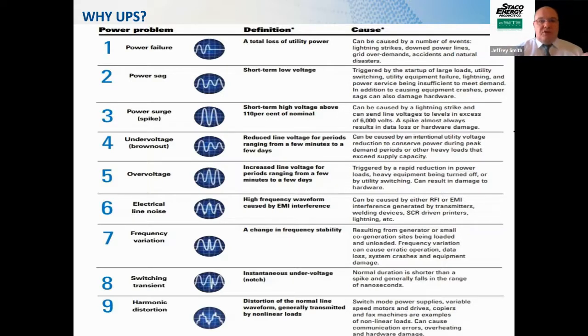The UPS system, we're able to keep the power up, and a lot of times without even going to battery in brownout situations. Over voltage situations, electrical noise getting on the lines, frequency variations. Typically, this is when you have a power outage, and in the United States, I'm talking mainly in power outage, then you go to generators. Sometimes the generators, if they're lightly loaded, they can vary a little bit with the frequency. Outside the country, we do a lot of this because we have a lot of customers all around the world where the frequency is not very stable.